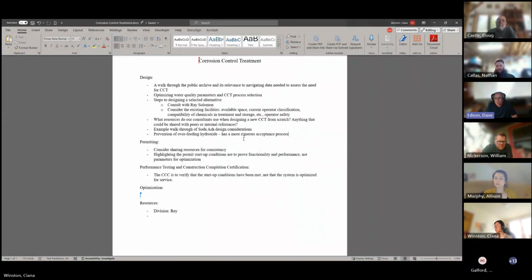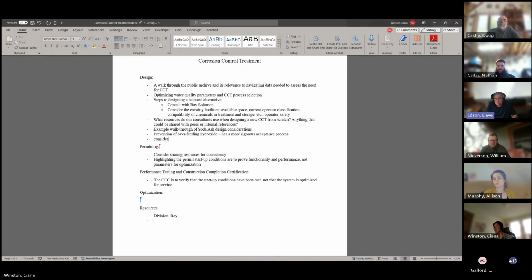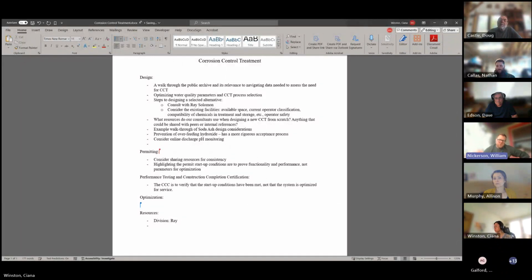Do you have online pH monitoring on the discharge? I don't think it's required. I would require it. If you're doing pH adjustment, I would require online pH monitoring on the discharge. Well, we have a lot of water systems that are adjusting pH with soda ash, and I think their only requirement is to record the pH every day.